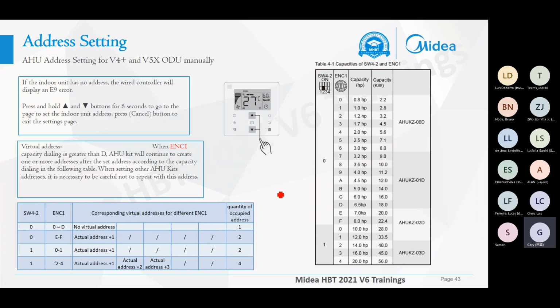Okay, the next part is also the most important part: the address settings. If the outdoor unit is the old generation, that is the V4 Plus, V6, and V5X outdoor units, especially the V4 Plus, as this unit has no auto addressing function, we should set the addressing for the AHU manually.